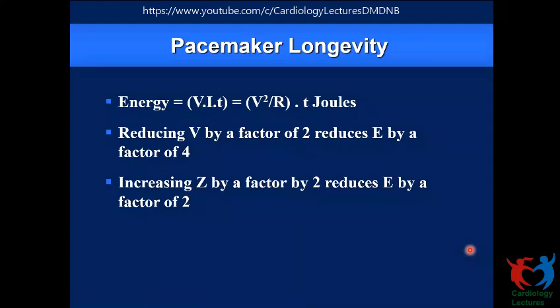That impedance is because the electrons come to the lead tip, and that is surrounded by the positive ions. So when you measure an impedance, it is impedance across the system. It includes everything: lead, tissue, and polarization. You don't get them individually. But by and large, what Mr. Govind is trying to say is that the lead impedance per se, because of current flow across the lead, is less. So it should be contributed by the tissue or by the polarization artifact. But you can't get individual values clearly. So what we measure is across the system, from the battery till the tissue. It could be anywhere. So if it is too high, then you have to deduce whether the lead wire is a problem, whether there's a conductor fracture across it, or whether there's a tissue impedance being very high or something else. Okay.